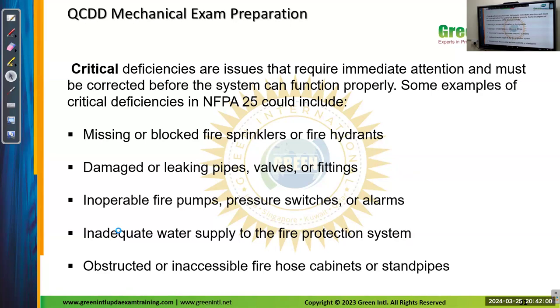Some examples of critical deficiency are missing or blocked fire sprinklers or fire hydrants, damaged leaking pipes or valves, inoperable fire pumps, inadequate fire water supply to the fire protection systems, and obstruction of fire hose cabinets. If you find any of these, the QCDD will not give you approval unless you replace all of this. So it is a critical deficiency.